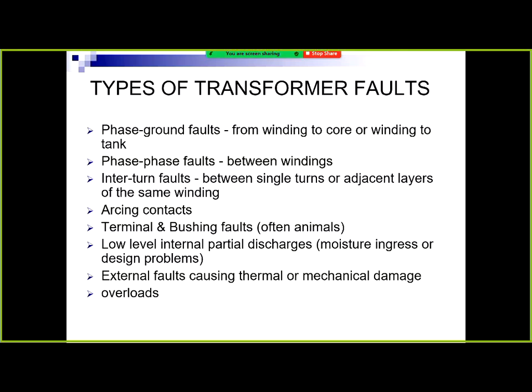So they were saying, 200 MVA side, you could put 200 onto that transformer and damage it. You go, no, you won't, but they go, you're not having your outage. So we said, what can we do? And they said, fix it up. So we had a portable overcurrent relay we just stuck in there and said, if you go above 150% of the rating of the transformer for longer than 10 seconds, trip it. So they were happy with that.